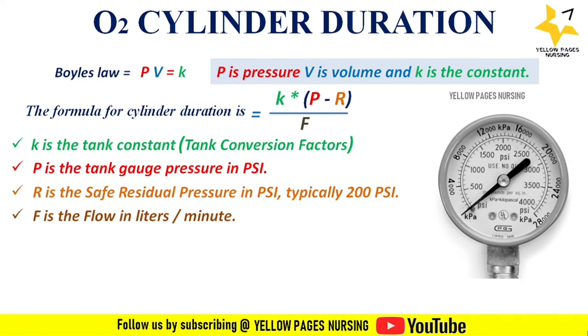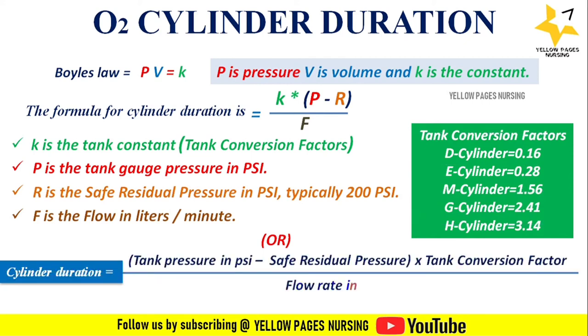We have one more formula to calculate the cylinder duration: tank pressure in PSI minus safe residual pressure, multiplied by the tank conversion factor, divided by the flow rate in liters per minute. You can use any of these formulas to calculate the cylinder duration. Let's have a look at an example so that you can clearly understand.